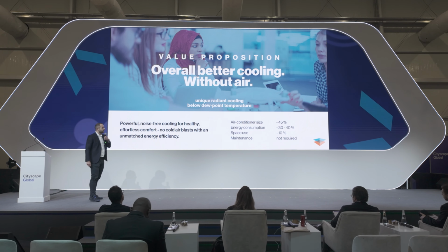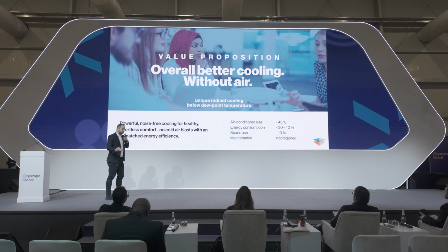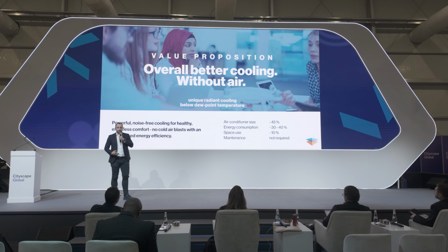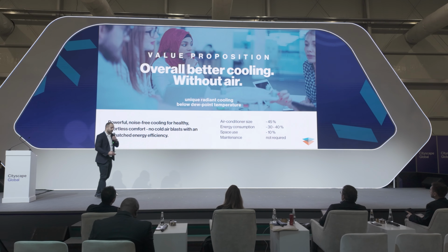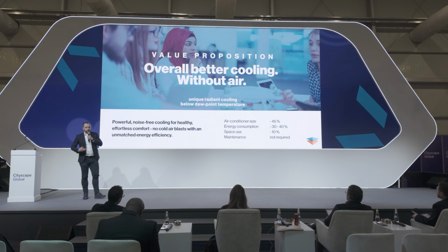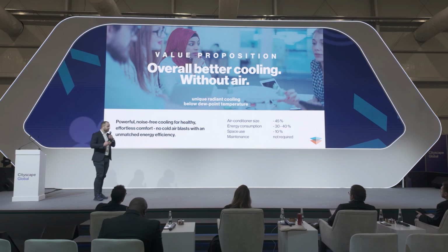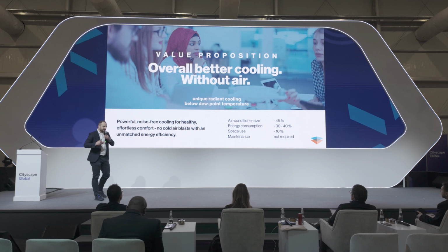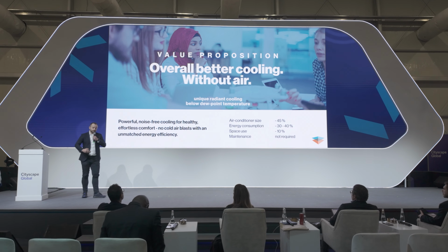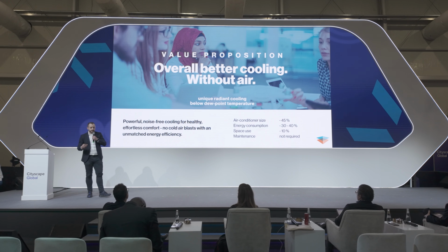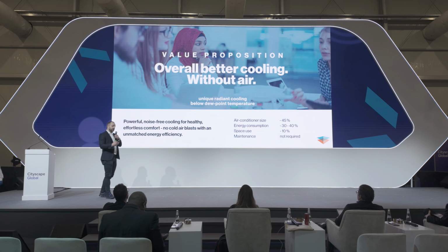So what do we do differently? Our value proposition is that we make better cooling without air. How do we do that? We use a radiant cooling technology which works independent from climate, dealing with the sensible heat of the building, the direct heat in a space, and not dealing with humidity and fresh air.